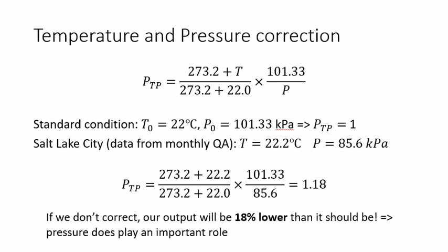Just to give you an idea, TG51 requires the output of a LINAC is within plus or minus 1% of unity. So 18% difference is a huge difference compared to the recommended tolerance.